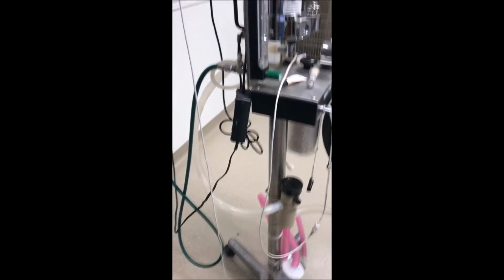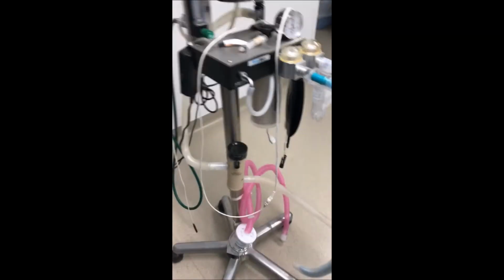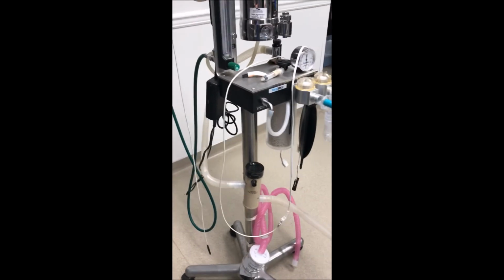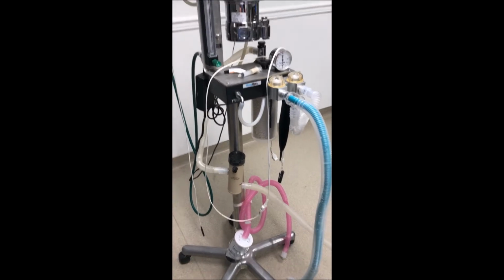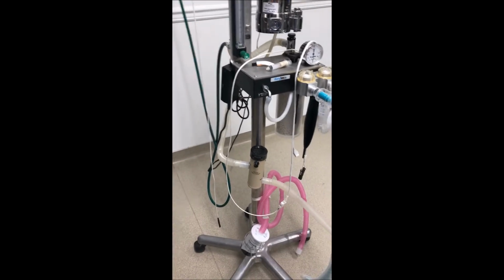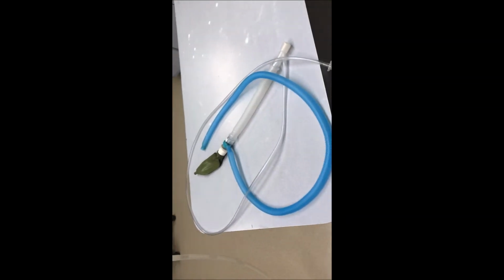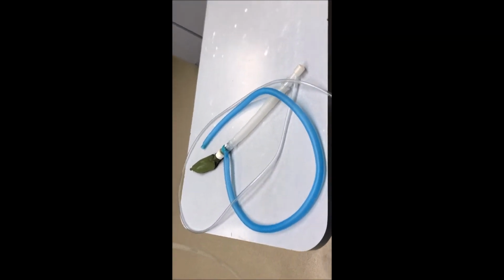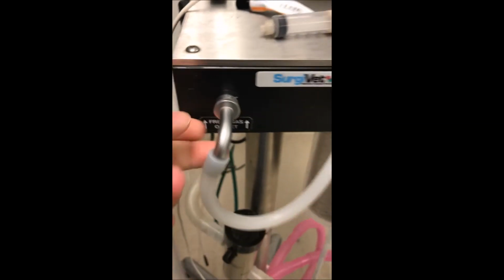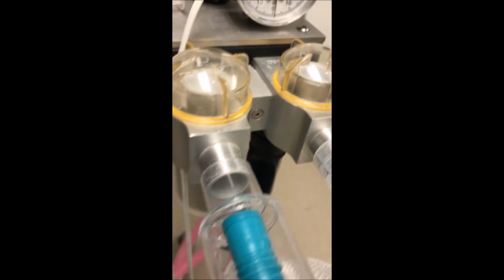In order to connect our non-rebreather to our anesthesia machine, this is something we use for very small patients. Anything under 5 pounds we recommend, or it is recommended, to connect your patient to a non-rebreather. So this is our non-rebreather circuit, and we're going to connect it. This end right here will actually replace the tubing for the fresh gas outlet. We'll connect that there. Next, this part will attach to the endotracheal tube on the patient.